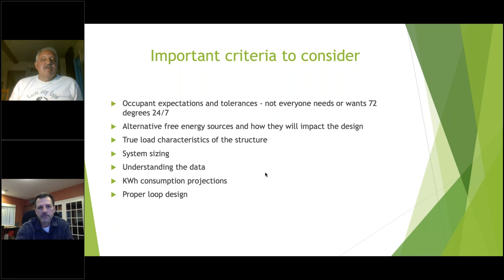We need to take that into consideration when designing and sizing the geothermal equipment. We also have to understand the true load characteristics of the structure. Proper heat loss and gain calculations are a must, and that will impact system sizing, sometimes dramatically. We need to understand the data, talk about kilowatt hour consumption projections, and also discuss proper loop design and how that impacts system operation.